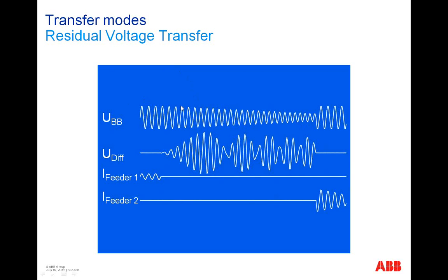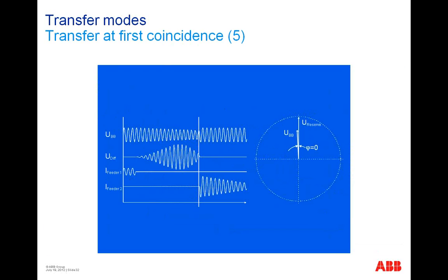So why 40%? I say, okay, we're waiting to a kind of 40%. Don't be confused, I step back to this one here to explain why 40%. So we're reverting only to 40%. So we don't have a look on the phase angle anymore. We say 40%, make changeover. What is the worst case in this moment? Yes, 40% with a phase angle in phase opposite with 180 degrees. Could be.